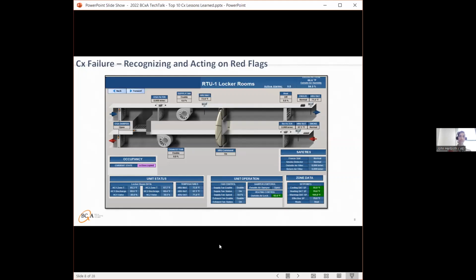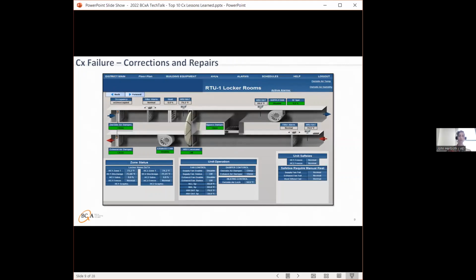So after this problem showed up, I got them to change the graphic to match what the field actually shows. And then they ended up installing a bypass damper and adding that functionality to keep that circulation going during morning warm up. Because I think that's what ended up, if I recall correctly, the morning warm up during that phase, that's when the coil froze. Things just weren't heated up. It started early. The heating water system wasn't operating the whole weekend like you'd normally do in a freeze condition outside, on top of the equipment failure and component failure.